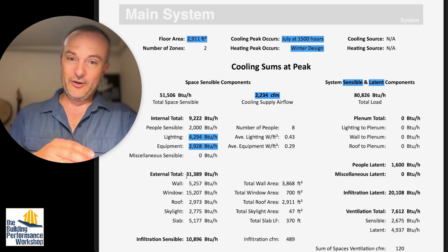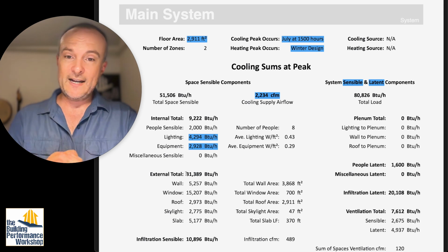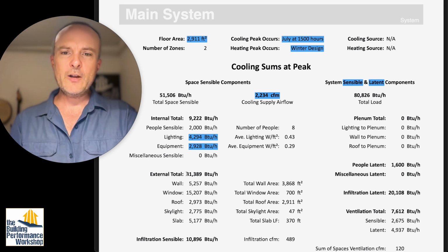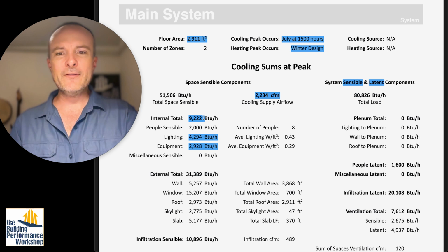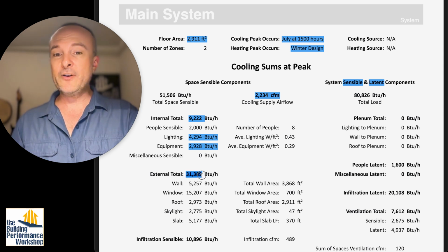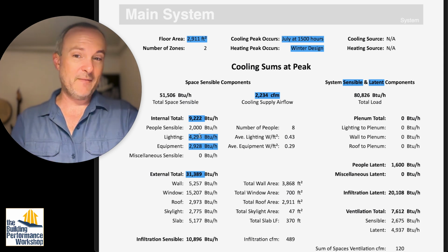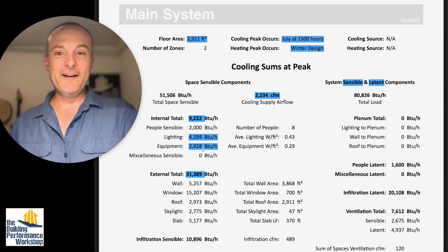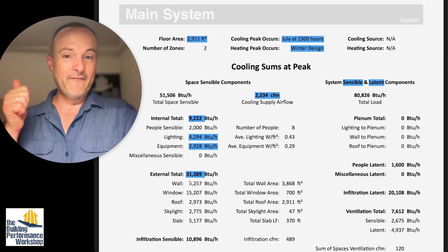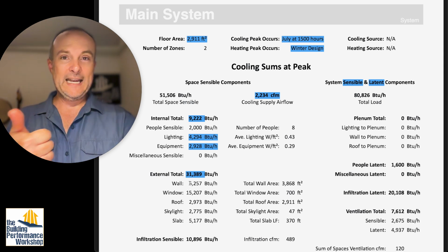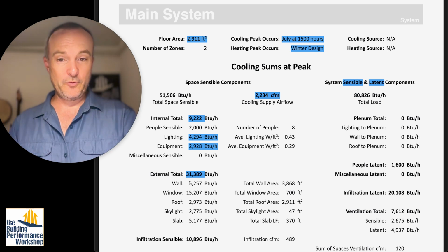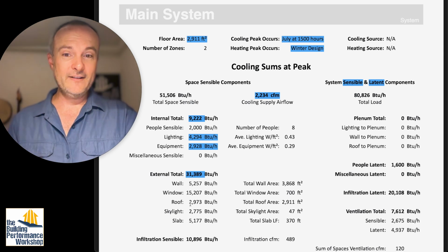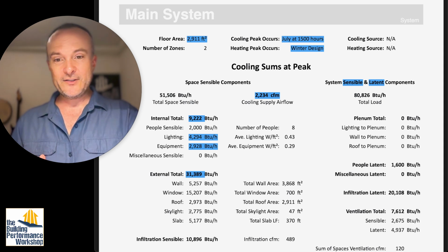Okay, so external total, this is stuff that is based on weather and the sun from outside. We have about 31,000. So inside we've got about, let's just say, 10. Outside we've got 31,000. That's quite a split. That's a lot of internal. We already talked about this. I would take about half off that to begin with. So there's that. As far as the external load goes, we've got 5,000 being sucked into the house, the heat being sucked into the house through the walls, 15,000 through the windows, 3,000 through the roof, 3,000 through a skylight.